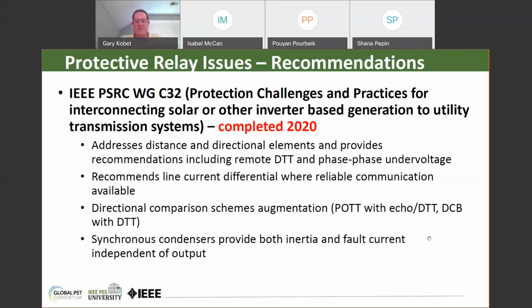And then there are a few other Power System Relay Committee activities that I don't have listed on a slide. There's another working group called C25, which is the protection of wind electric plants. The D29 working group I mentioned just a second ago, which is a tutorial on setting impedance-based power swing blocking and out-of-step tripping functions. And then D38 I mentioned, which is the impact of high source impedance ratio on distance relay. And I'll also mention there's another IEEE guide that the Relay Committee put together called C37.246, which is titled The Guide for Protection Systems of Transmission to Generation Interconnections.